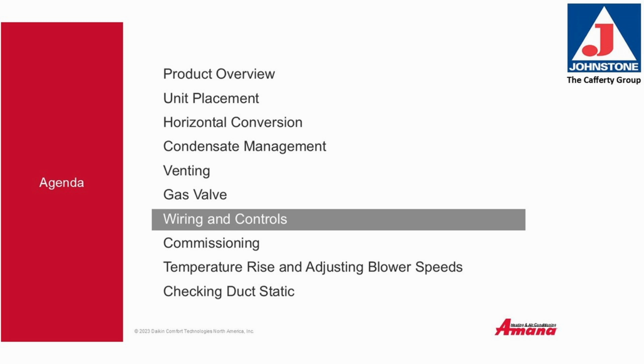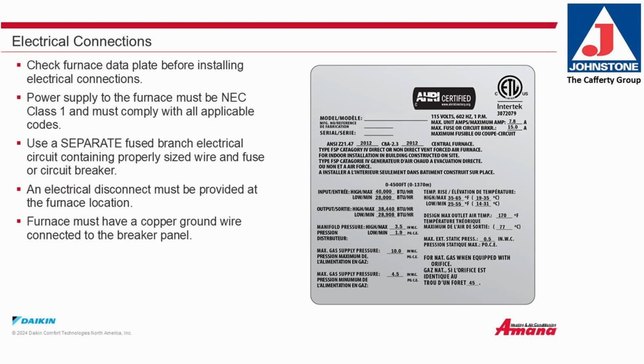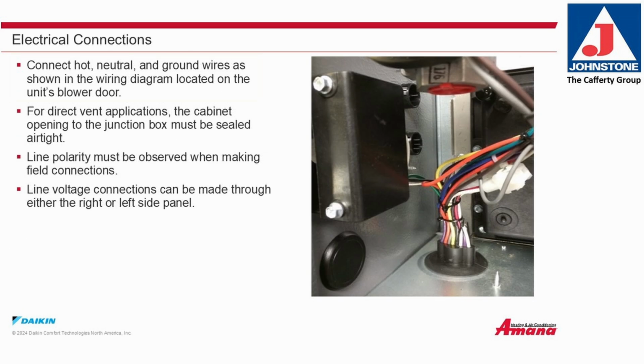Now let's look at wiring and controls. Electrical connections. Check the furnace data plate before installing electrical connections. Power supply to the furnace must be NEC Class 1 and must comply with all applicable codes. Use a separate fused branch electrical circuit containing the properly sized wire and fuse or circuit breaker. An electrical disconnect must be provided at the furnace location. Furnace must have a copper ground wire connected to the breaker panel.